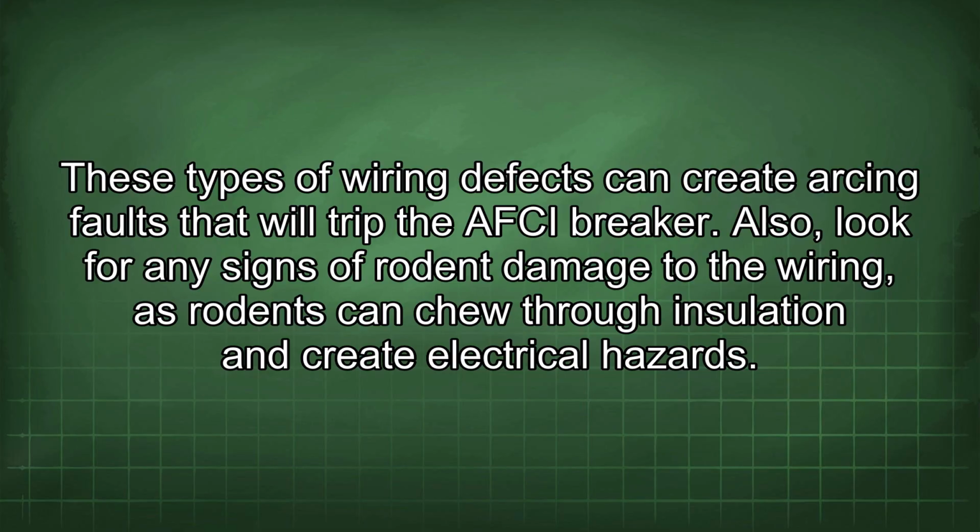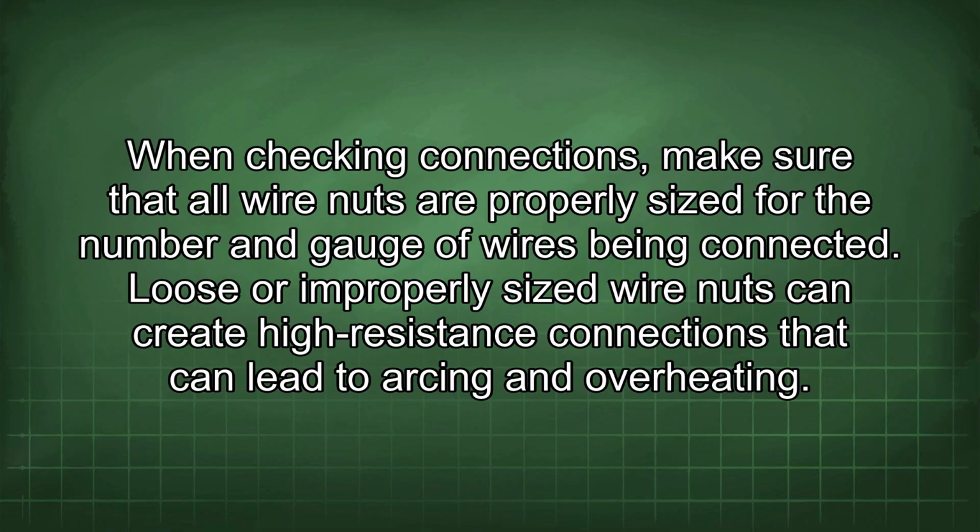Also, look for any signs of rodent damage to the wiring, as rodents can chew through insulation and create electrical hazards. When checking connections, make sure that all wire nuts are properly sized for the number and gauge of wires being connected. Loose or improperly sized wire nuts can create high resistance connections that can lead to arcing and overheating.